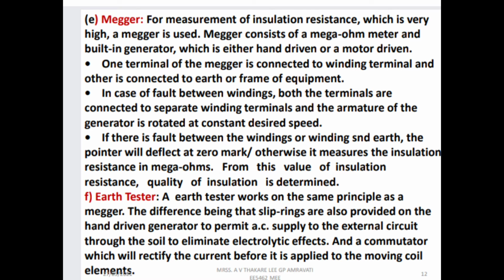For measurement of insulation resistance which is very high, a megger is used. Megger consists of a mega ohmmeter and a built-in generator which is either hand driven or motor driven. One terminal of the megger is connected to the winding terminal and the other is connected to the earth or frame of equipment. In case of a fault between windings, both the terminals are connected to separate winding terminals and the armature of the generator is rotated at constant desired speed.